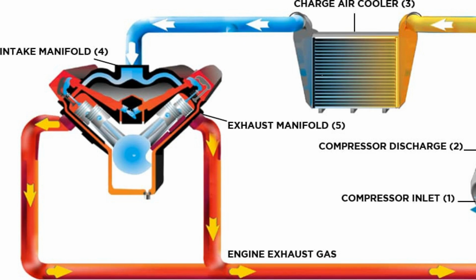This fault can be detected by a sudden drop in power and increased fuel consumption. If the spigots broke from the pressure, it is not worth trying to repair them, since a new pressure surge will break them again. It will be necessary to change the spigots.